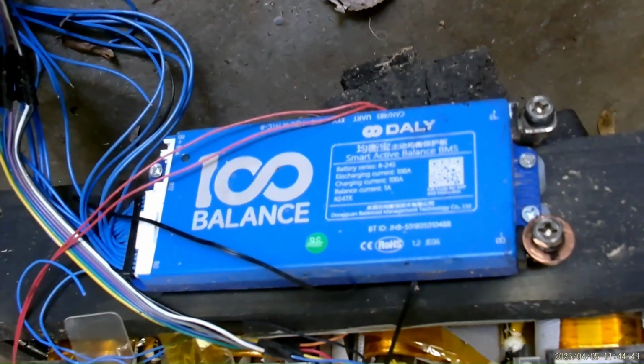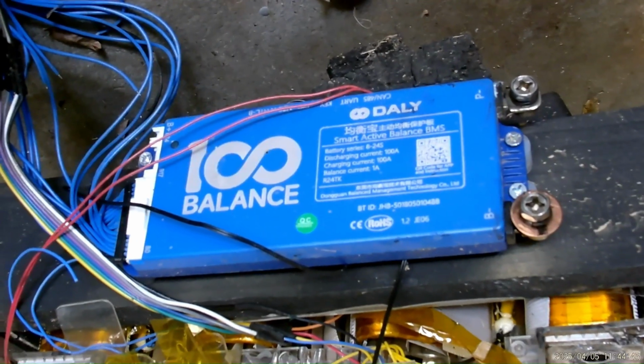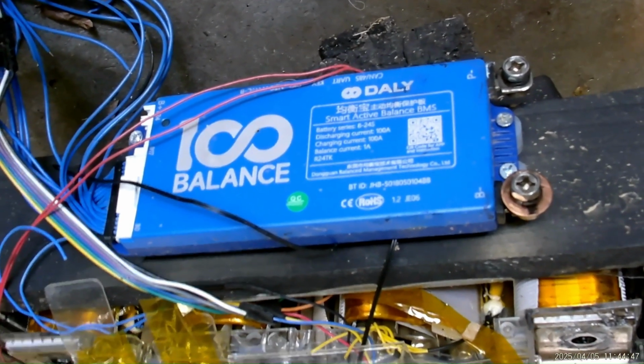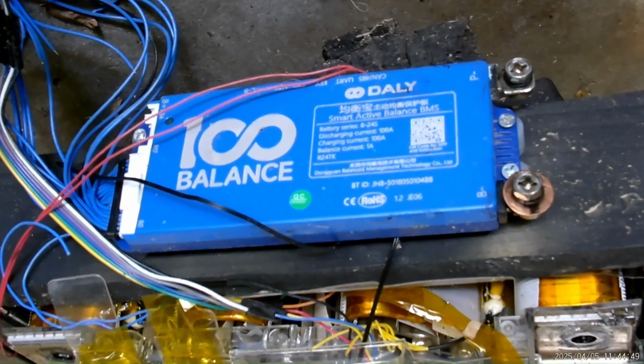The cells in a bank are in parallel, so their voltage will all be the same. If they're not, the fuse link will blow. But if I charge the 24-volt battery, one bank may be at a higher voltage than the others, and that would allow overcharging it. So we use a battery management system like this one to keep the banks at the same voltage. Take a look at this schematic.